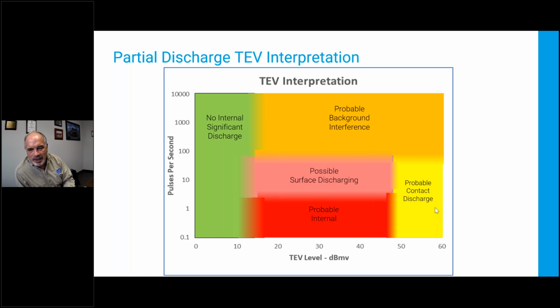My favorite example of this is a set of switchgear we had with full-time monitoring on, brand new switchgear, brand new cables. We energized the switchgear, everything's up and running. A couple days later, we got the monitor running, and in one cabinet, we had 50 dB, 50 pulses per cycle. Shut it down, what's going on? We opened up this cabinet, it was a cable compartment, and inside the cable compartment was a Home Depot bucket full of tools. Because the tools were in a bucket, they were insulated, but the metal on the tools created this massive discharge effect, which prevented us from seeing anything smaller.